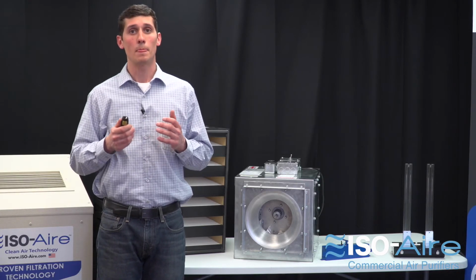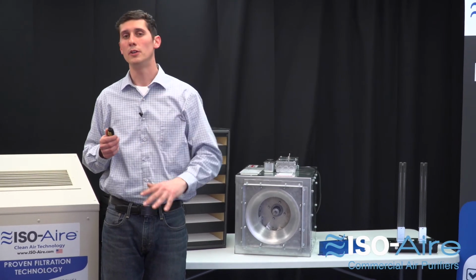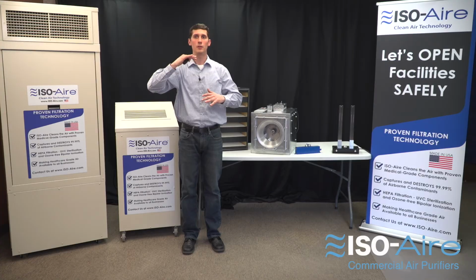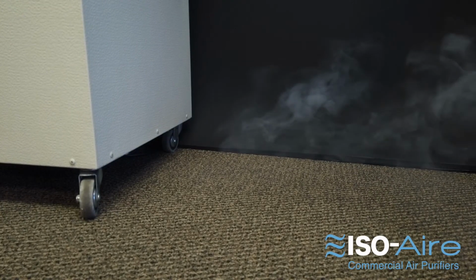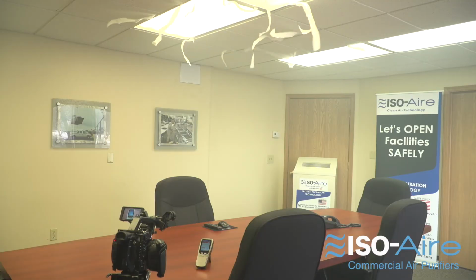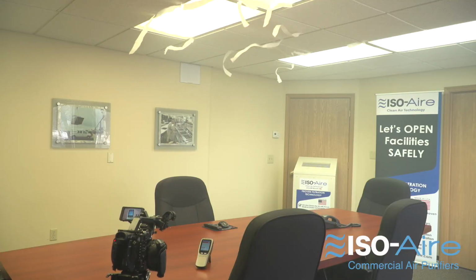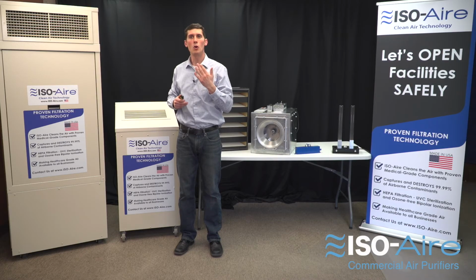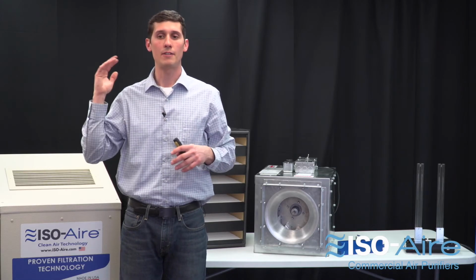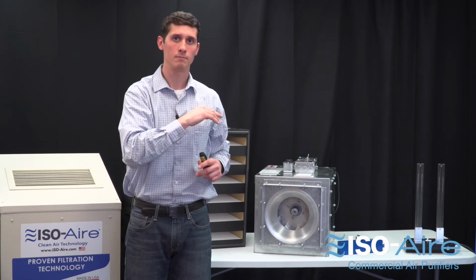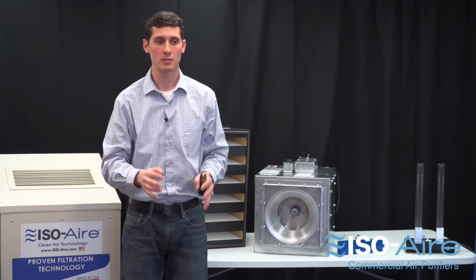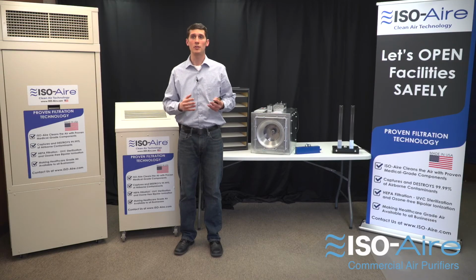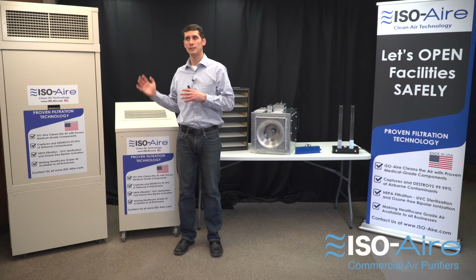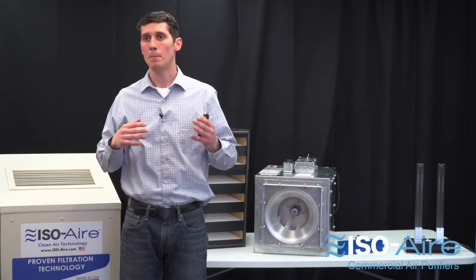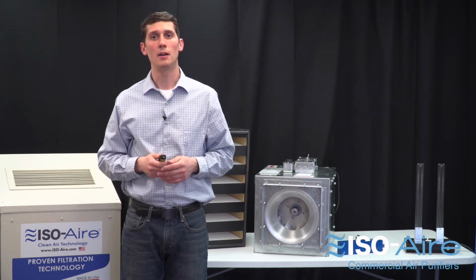Someone's asking why we pull low and distribute air high. The main reason is to get the contaminants out of the breathing zone. You want to pull it away so you've got clean air to breathe, getting those contaminants down low into the units to be captured. You're distributing that air high across the ceiling so you're able to reach throughout the room and distribute clean air. What you don't want to do is blow dirty air — let's say I'm sick — right across my face and into the next person. A lot of small, inexpensive units simply blow air out the top, not being able to properly distribute that air. With our pull low and blow high design, and the right fan power, we're able to solve that challenge by providing the proper air mixture flow.